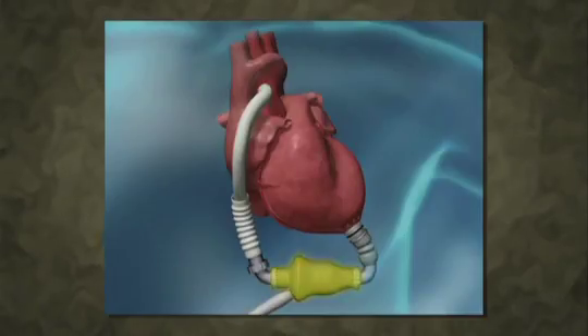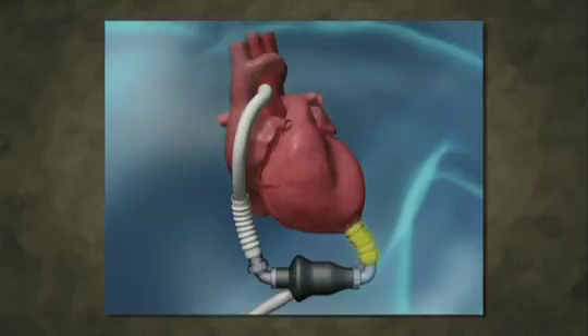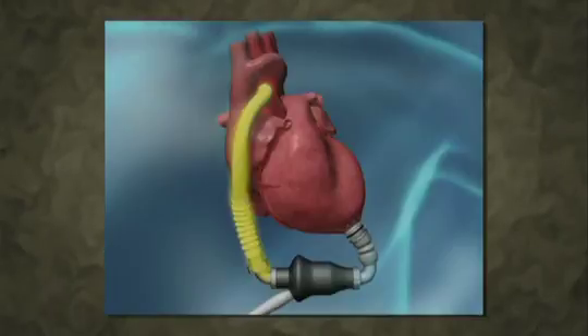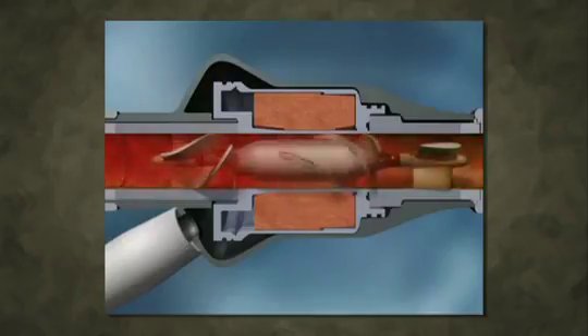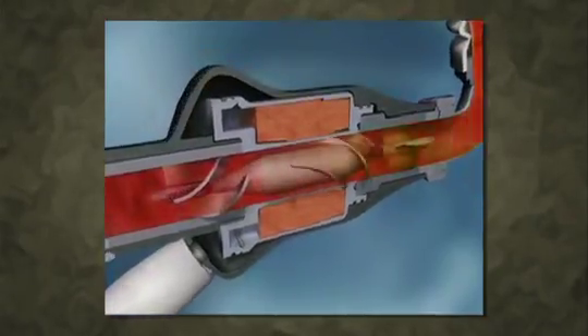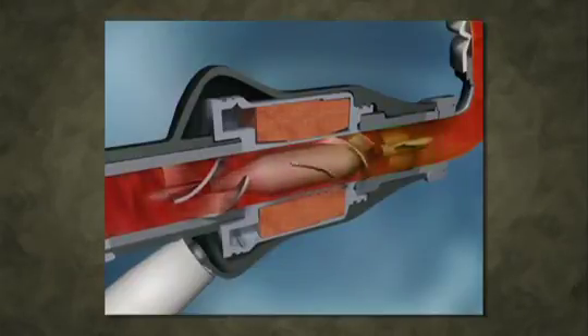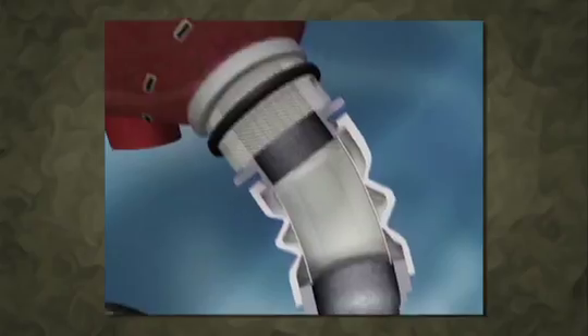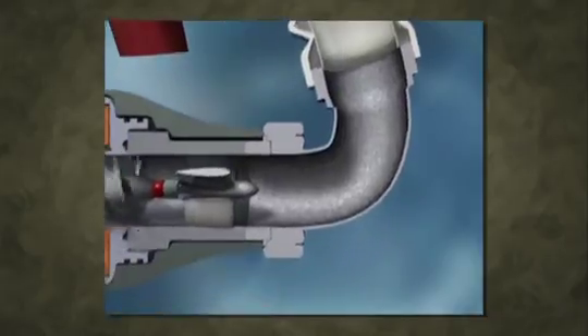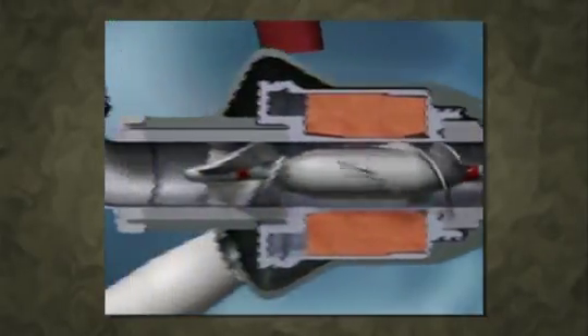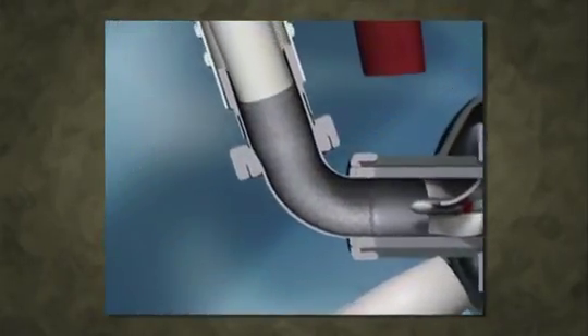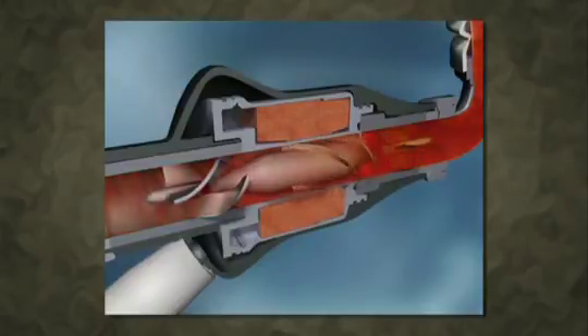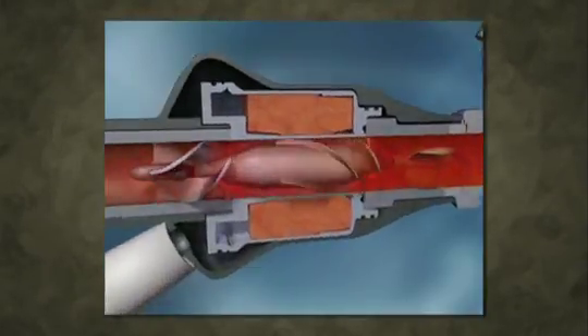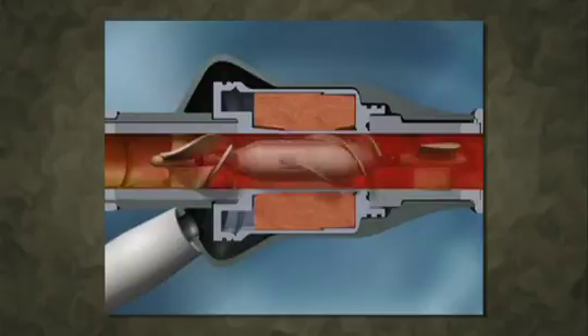The pump is connected to tubing on one side to the apex of the heart in the left ventricle. The opposite side of the pump is connected to tubing that connects to the aorta just above the aortic valve. The pump will assist with the moving of blood through the body. A small electric motor inside the LVAD drives the pump. The LVAD has only one moving part, a small spinning rotor that receives power from the system controller. Vanes on the spinning rotor move blood through the pump, which is capable of providing flow between 3 to 10 liters per minute.